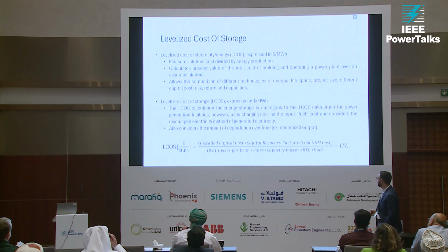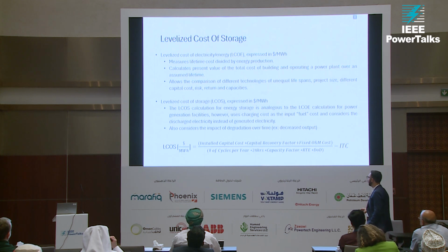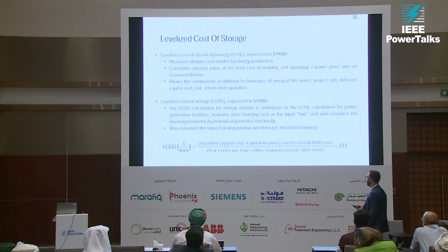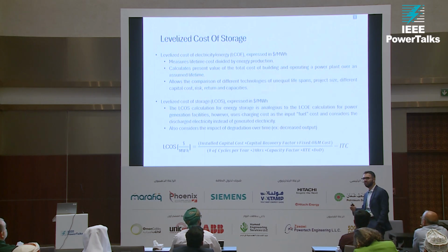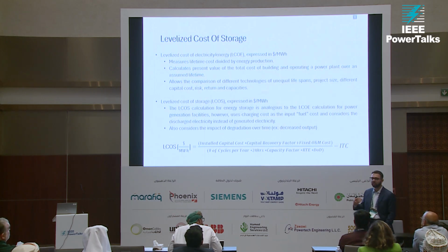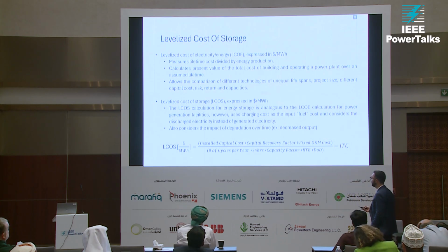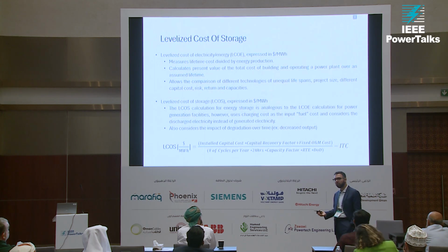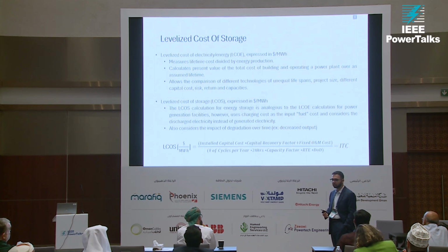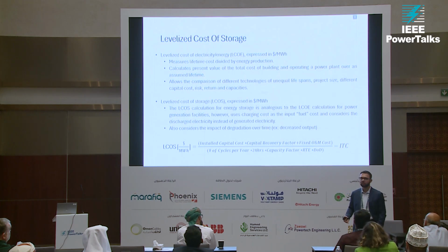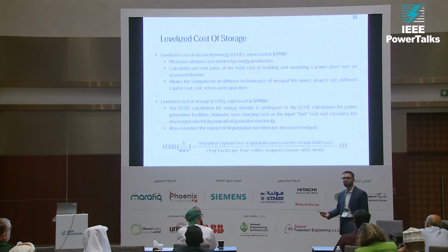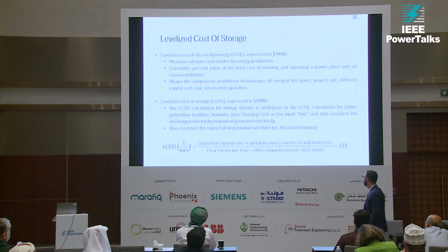The levelized cost of storage gets a little bit more complicated. It's still your cost of installation and your cost of operation, but then you start adding quite a few things. Now you don't have energy delivered, right? You're not generating new energy. You have energy charge and energy discharge. So you start measuring it by how many cycles you expect the system to run. When you start evaluating a project, is this a system that's going to be running every day, or a system that's going to be running once a month? That's really the measure you start looking at.